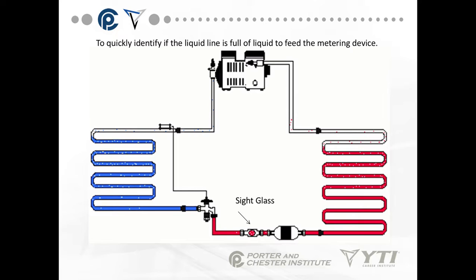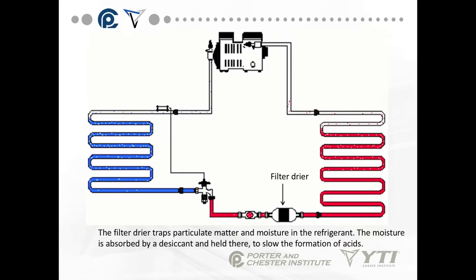There are some additional components you don't see in every system. You have a sight glass, which allows you to basically see into the refrigeration system. Do not use this as a method of charging or evaluating a system. A sight glass also has a moisture indicator inside of it — that is probably the most important part. Do not count on a sight glass for proper charging.